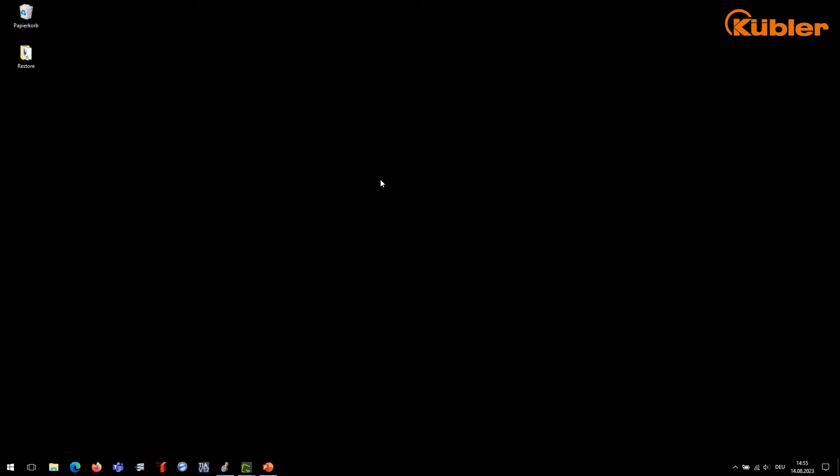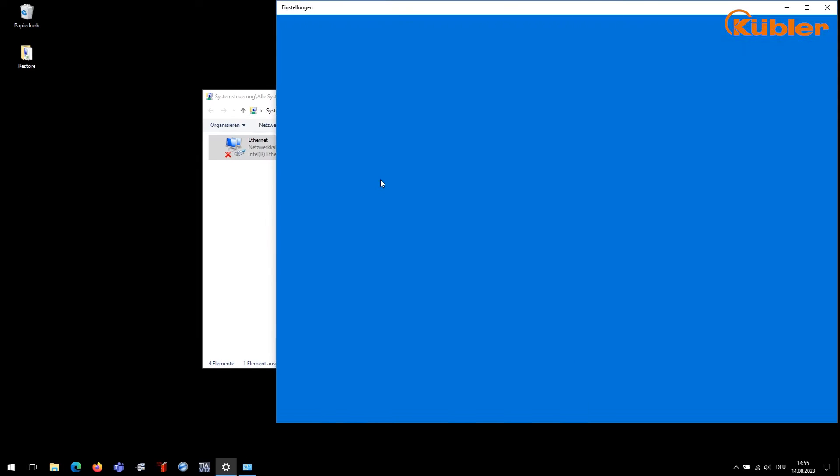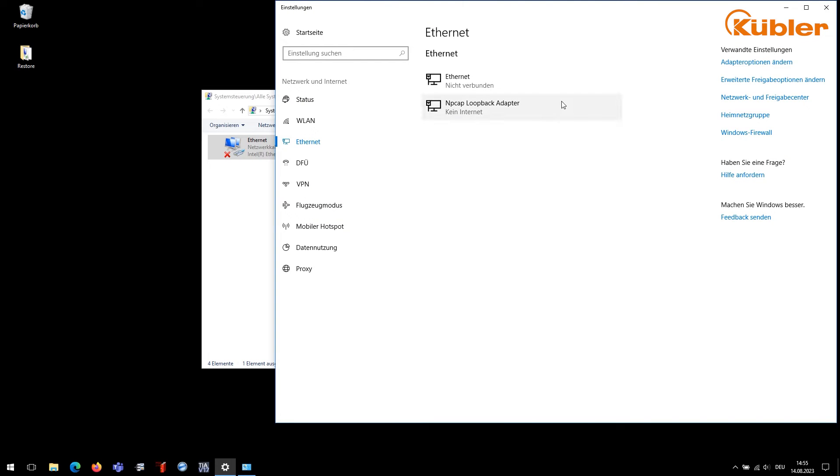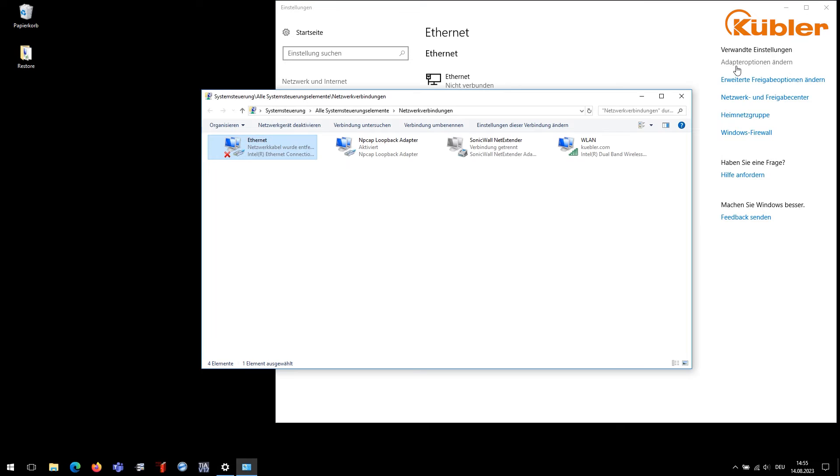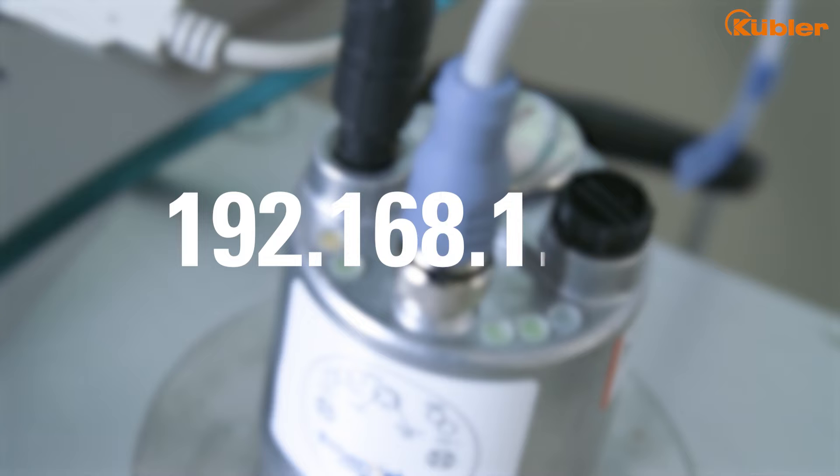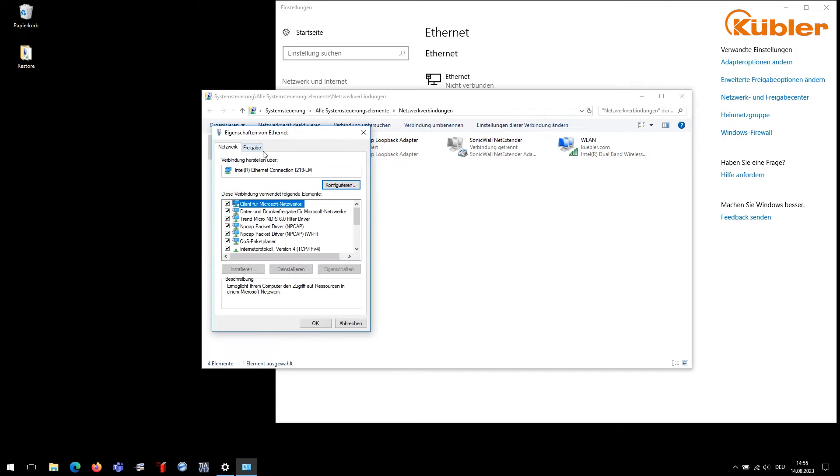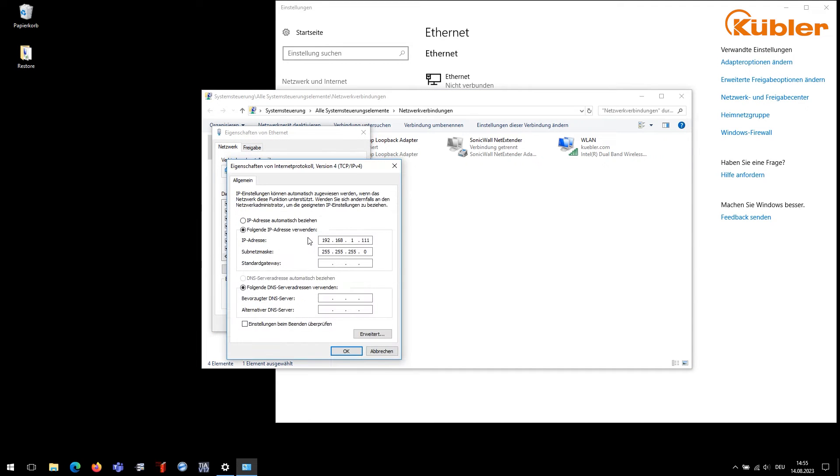It is essential to set the correct network settings. First, we have to define a valid IP address for the supervisor PC. The default subnet of the encoder is 192.168.1.xxx. In order to establish a connection to the device, the supervisor PC has to be in the same subnet. Go to the PC network settings and use the IP address 192.168.1.111.